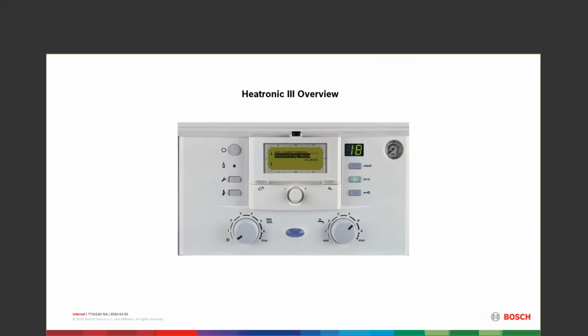Normally you would see it would be a blank in the middle, so there would be no extra screen, no extra knob in the middle. That whole piece would be missing. And you would add this FW200 as an outdoor reset control. We've eliminated that or taken it out of production. And now the chosen control for this would be the CRC 200.